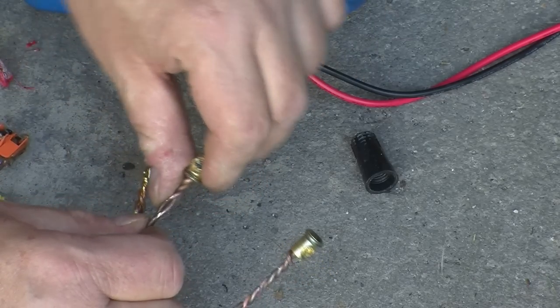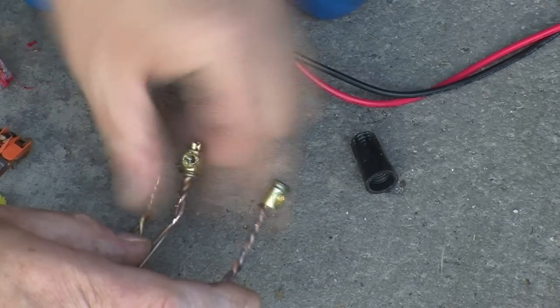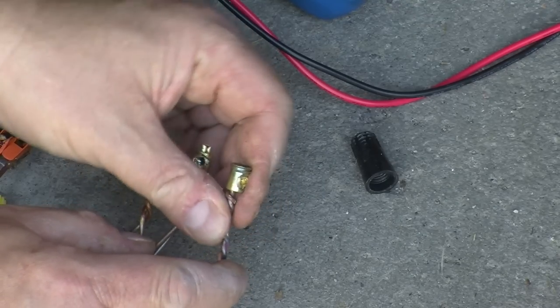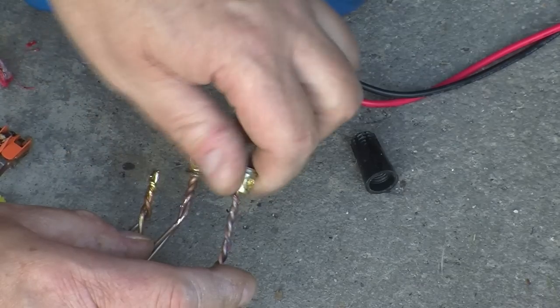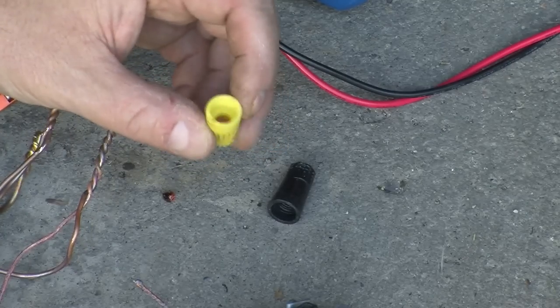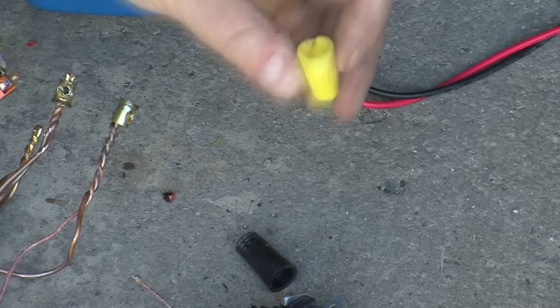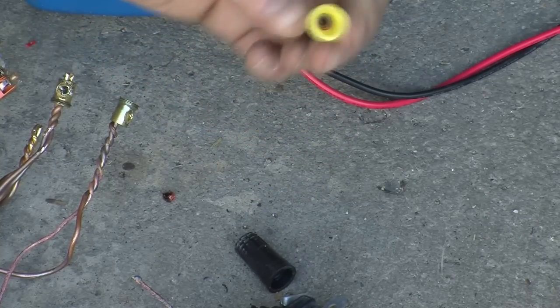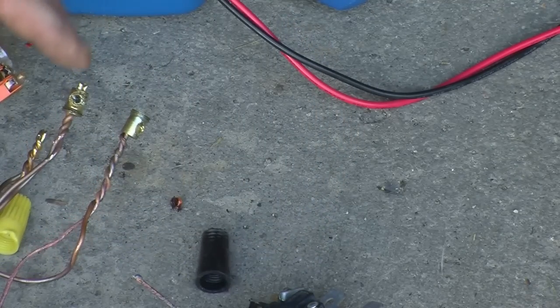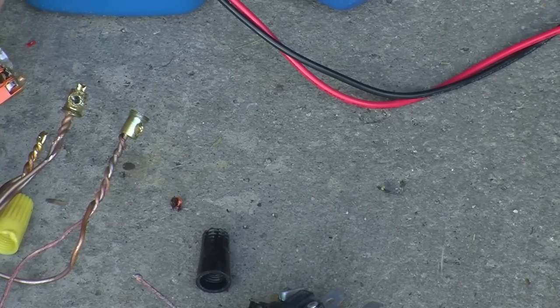So, the final conclusion is you cannot beat wire nut type connectors. As old as they are and as low tech as they are, they stand up to an incredible beating and overcurrent and survive amazingly well. So with the simplicity and cost and excellent performance of wire nuts, they really should remain the most common form of electrical connection for things like household wiring. Well, that brings this video to an end. See you next time.